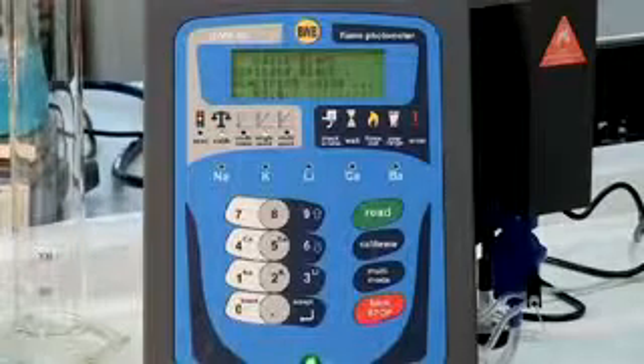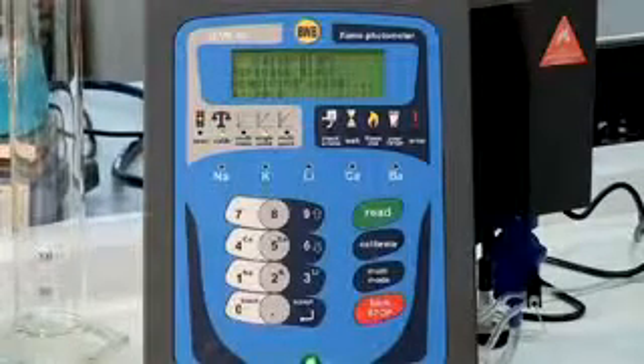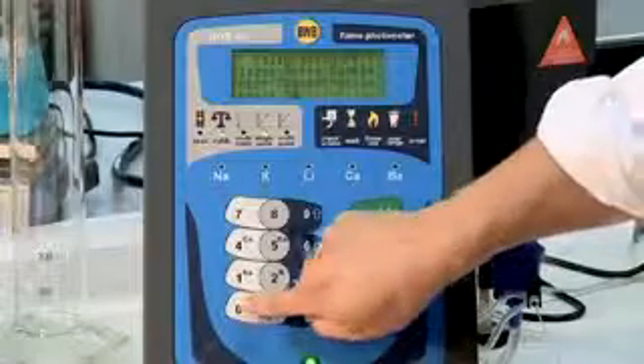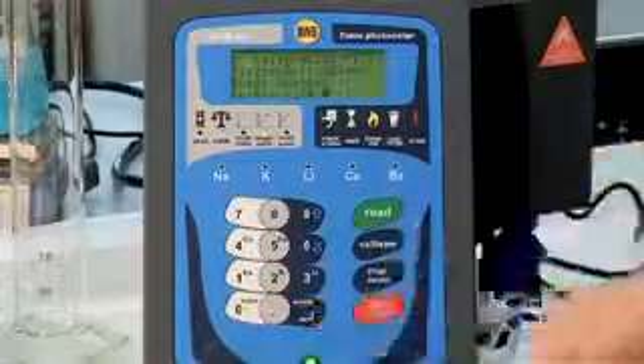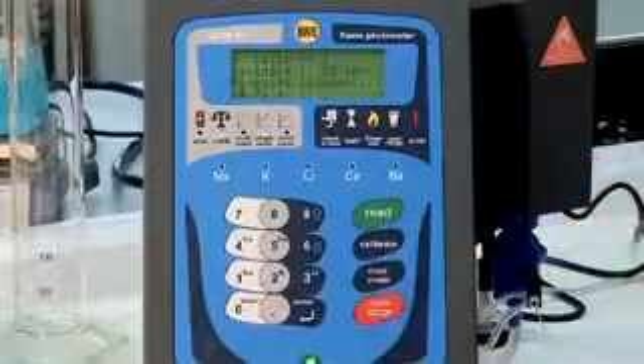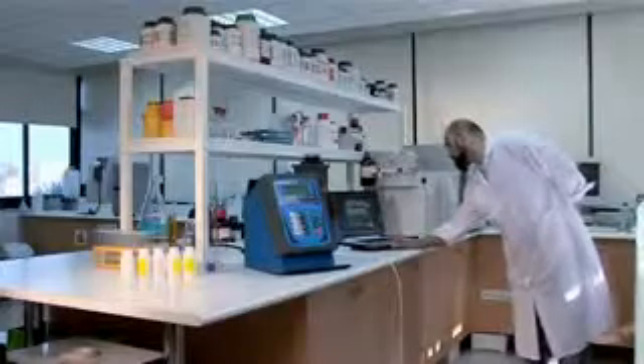There are three types of calibrations we can do: single point, multi-point and multi-mode. We will start with the most common type, the single point calibration. The single point calibration involves one standard and a blank to set the 0 point. Of course, all calibrations require a blank to set the 0 point. Let's do a single point calibration of potassium at 50 ppm, and while we are calibrating, we can use the FP PC software to follow along.